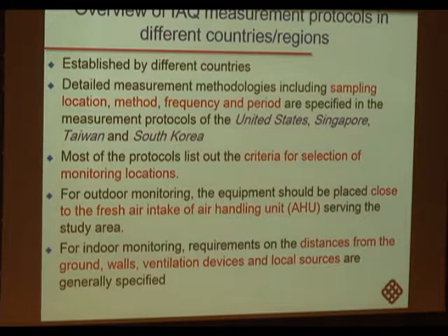So for the different sampling locations, some specify, some do not specify. How frequently you do the measurement, even the period, 8 hour, 1 hour, 4 hour, it all varies. Most of the protocols list out criteria for a monitoring location. For example, even in Hong Kong, we satisfy. Even outdoor, you get to do monitoring. And some guidelines do have a certification request that it be close to the fresh air intake or even the air handling unit. And for an indoor air monitoring location, there are some specifications on distance from the wall, ventilation device, local sources, all of which have been specified.